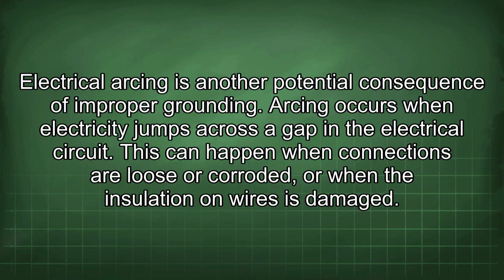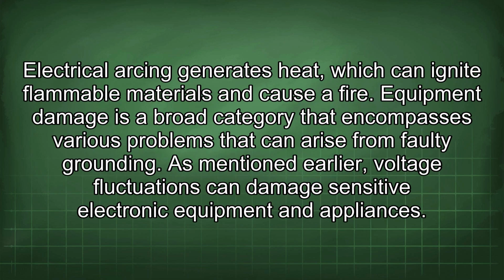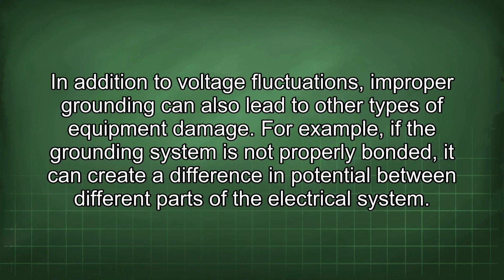Electrical arcing is another potential consequence of improper grounding. Arcing occurs when electricity jumps across a gap in the electrical circuit. This can happen when connections are loose or corroded, or when the insulation on wires is damaged. Electrical arcing generates heat, which can ignite flammable materials and cause a fire. Equipment damage is a broad category that encompasses various problems that can arise from faulty grounding. As mentioned earlier, voltage fluctuations can damage sensitive electronic equipment and appliances. In addition to voltage fluctuations, improper grounding can also lead to other types of equipment damage.